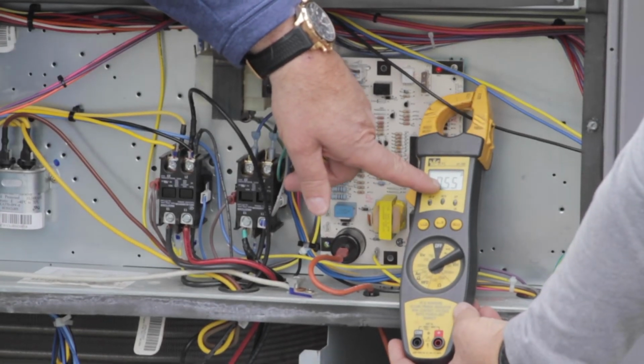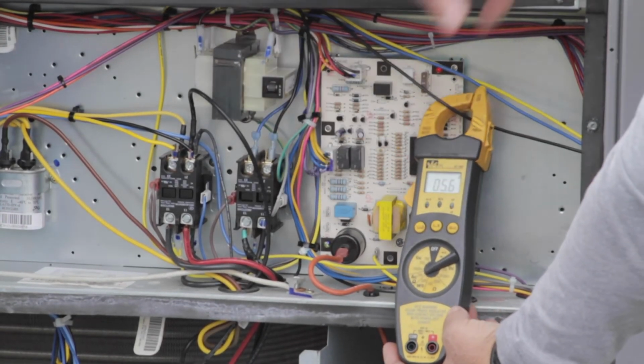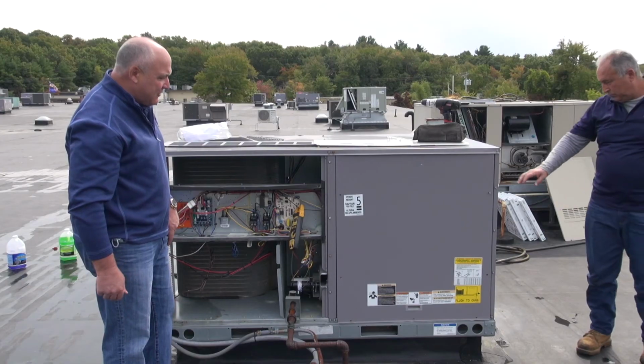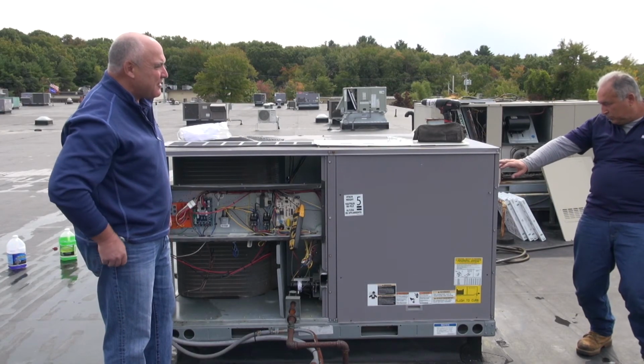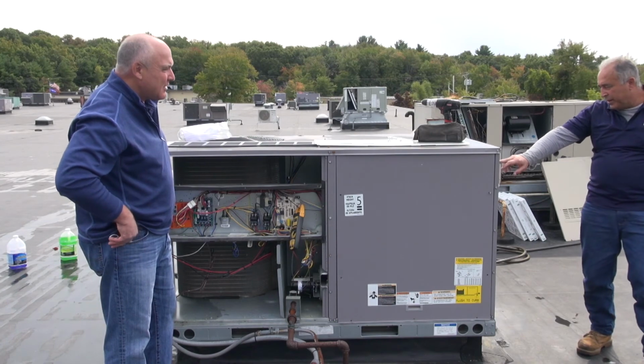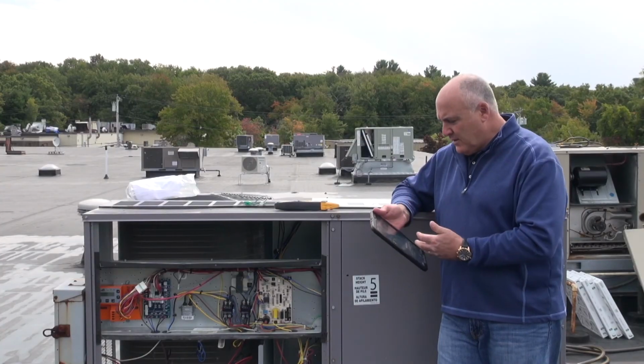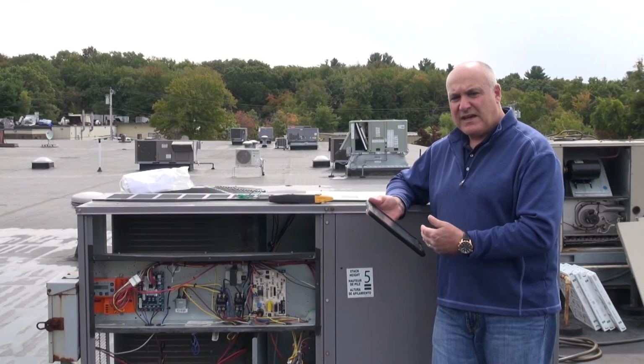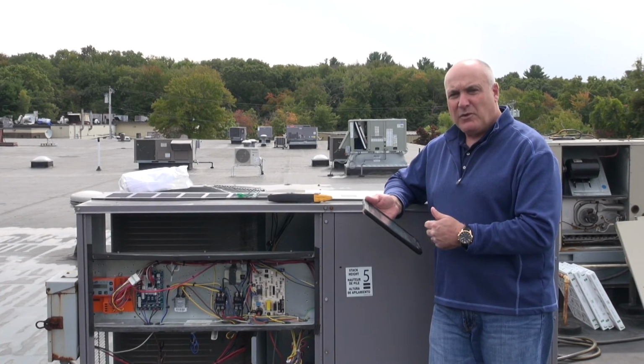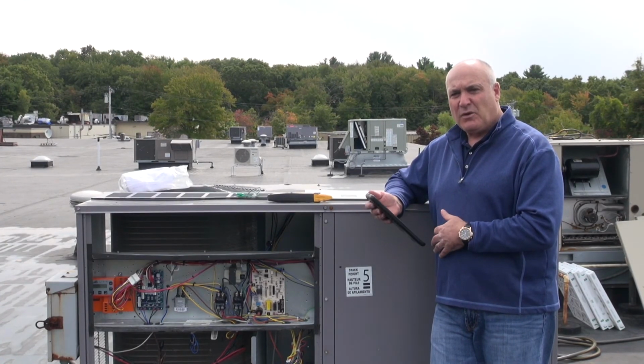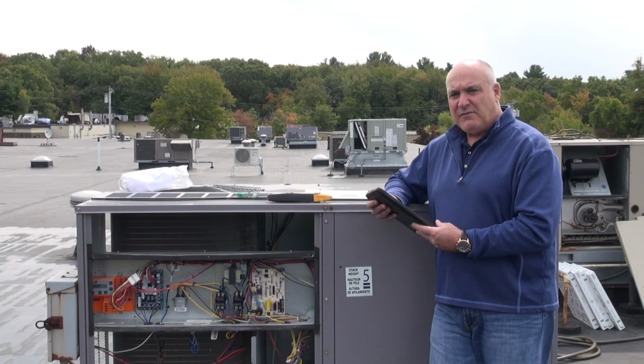Using an amperage meter, we also check to make sure the blower motor is drawing the correct number of amps as shown on the nameplate of the unit. Finally, we log all of the information about the inspection on our tablet, so that we have a complete record of all maintenance work done on the rooftop AC unit throughout its life.